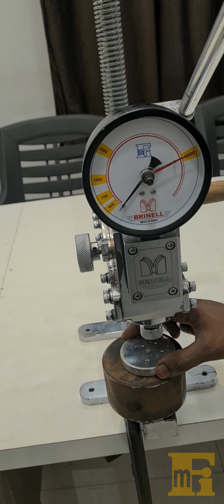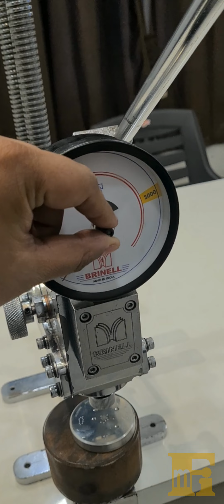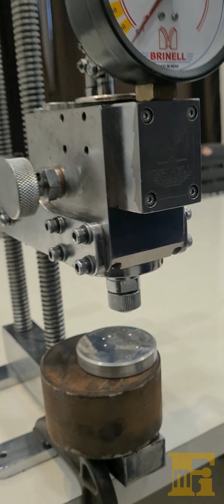Now we will change the configuration of the machine to test with 1000 kg test force, Brinell hardness test. To change the load, use this load selection knob valve. Rotate it anti-clockwise 1/2 turns. Now the machine is set to perform the test with 1000 kg load.